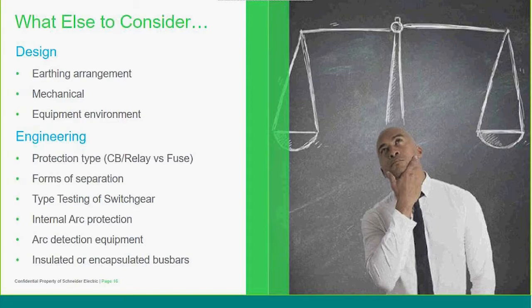And another area that we're seeing quite a lot of is encapsulated bus bars at medium voltage. This is where you have an earthed screen encapsulated bus bar. Again, if there are any failures of the bus bar system, in theory the fault will be shunted to earth and should be safe for an operator. So there's quite a few other things to consider when thinking about arc flash and incident energy levels.